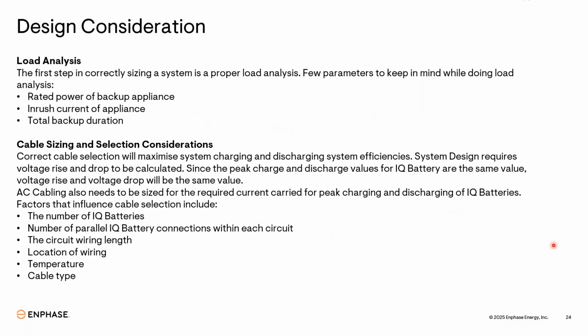Design consideration. Before installation, once you are doing the site surveys and suggesting a backup solution to a homeowner, we recommend you get complete details about the loads and the backup times. Sometimes we get inquiries like a customer wants to install a 30 kilowatt plant, and he wants backup for that also. We say okay, 30 kilowatt is a PV plant, but what load does he want to back up? They say he wants 30 kilowatt completely, and for how many hours? Generally 8 hours. So there are no exact details about the loads, and it's simple: he wants a 30 kilowatt backup for 8 hours.